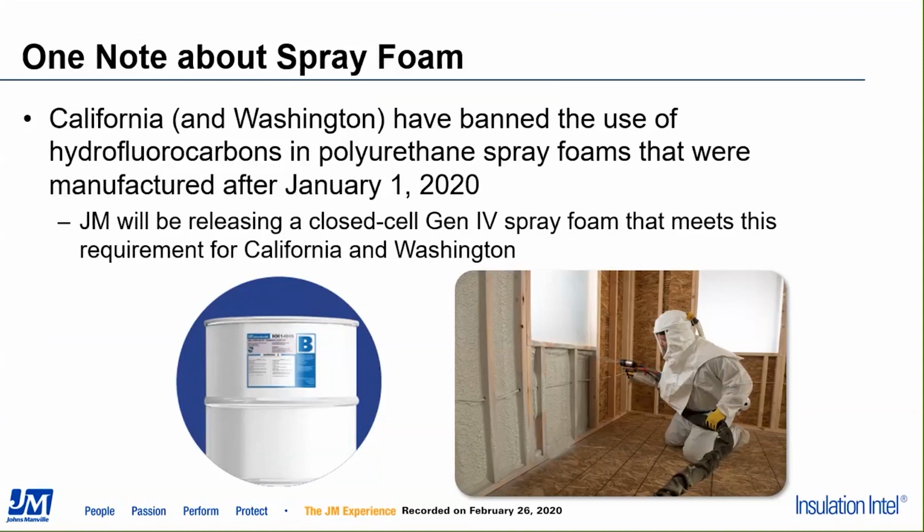So if I want to use closed cell foam, there is still a JM option that will be available to you. Open cell foam, which honestly is the more common product that we see used in California, is not affected because the blowing agent for open cell foam is just water. So there's no HFCs involved, and that product is not impacted by this change.